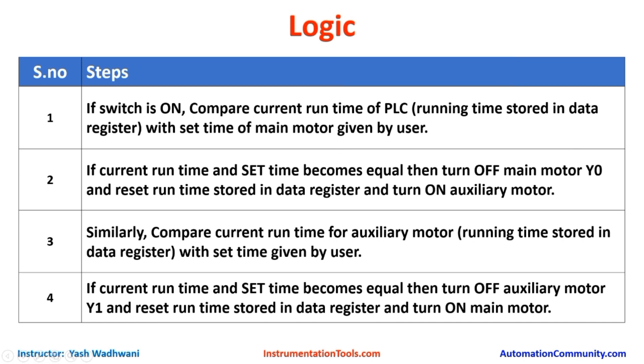Now let us understand the logic required to create this project. When the switch is on, we compare the current running time stored in a data register to the set time of the main motor given by the user. When they become equal, output Y0 turns off and the running time in the data register is reset. After that, the auxiliary motor turns on. Similarly, we compare the running time of the auxiliary motor with its set time. When they become equal, the auxiliary motor turns off, its run time resets, and the main motor turns on again.